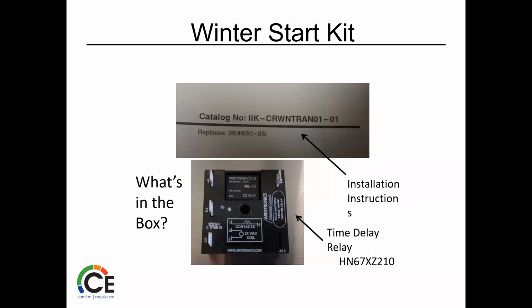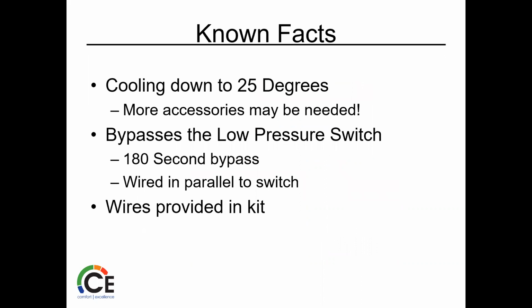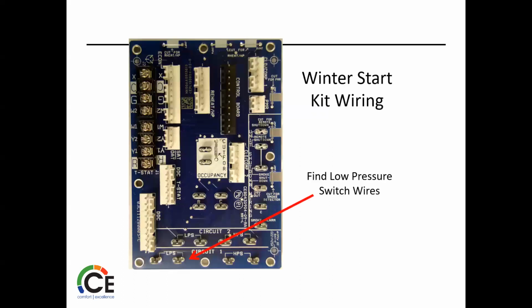So we talked about that winter start kit. This is just a relay, a time delay relay. It does come with instructions, take them or leave them. They're there. Cooling down to 25 degrees. More accessories may be needed. Again, it just depends on what you're using it with. Bypass is the low pressure switch, and it's wired in parallel. Once we get to that, I'll show you one of the big mistakes people make, because then we come back in normal cooling season, and now this thing's not working because of what they've done. The wires are in the kit, so it helps out.